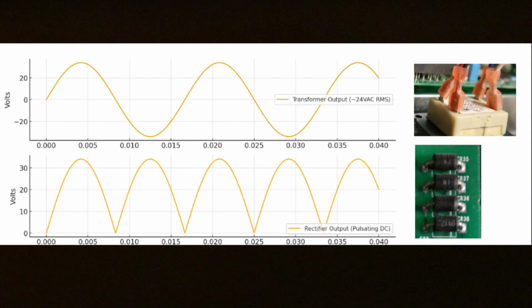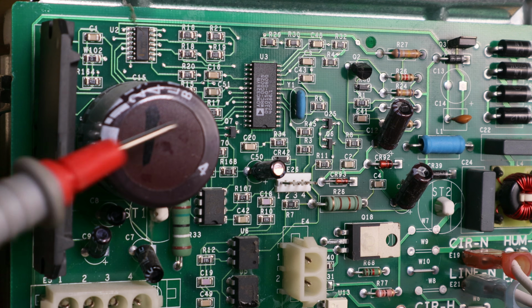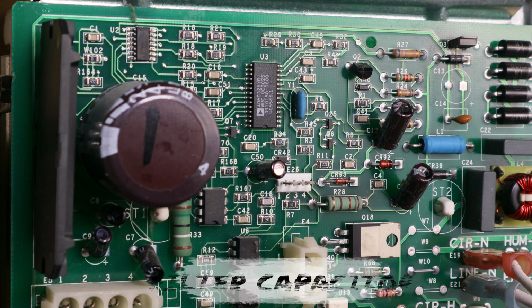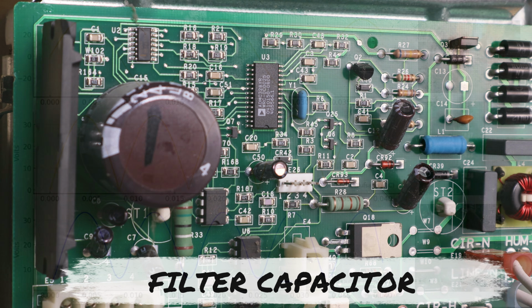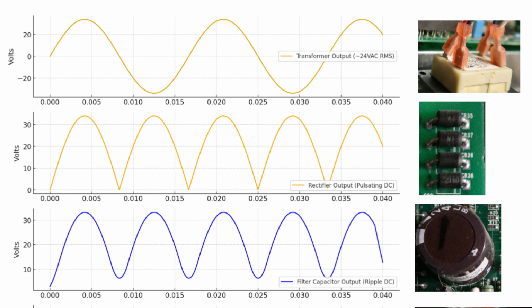Now, these variable speed motors are very precisely controlled. And in order to get that precision control, we need a very clean and stable signal. This is the beginning of it, but this pulsating DC wave is too sloppy. It's fluctuating too much. We need to clean it up even more. So our next step is this brown cylinder here, and that is a filter capacitor. It takes that pulsating DC wave coming off of the diode bridge and turns it into a nice smooth, what's called a ripple DC wave. So it's smoothing that signal out.